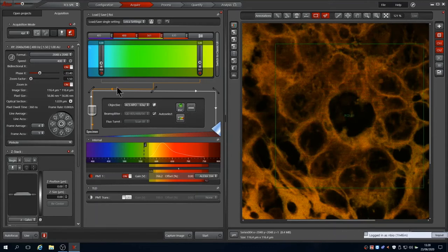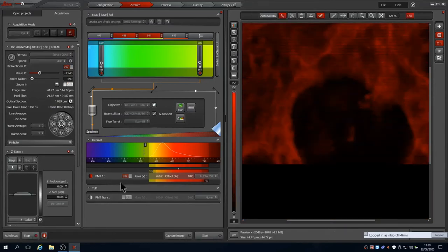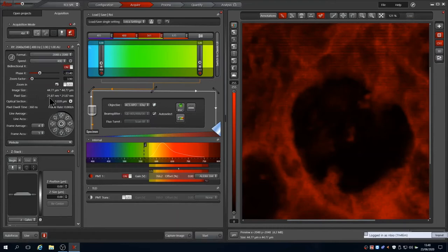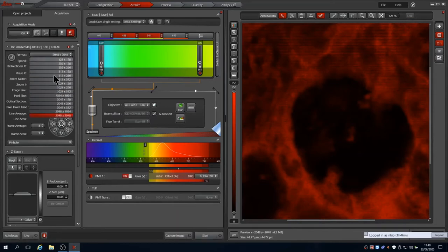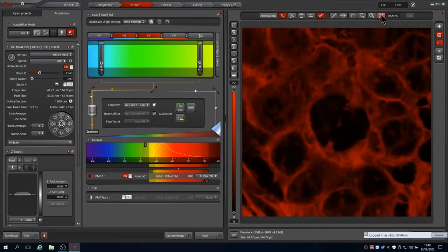The software will still keep the global XY parameters we set, so we'll still get a square scan to fit the area and at the same pixel density. This means our pixel sizes are now very small, meaning we are heavily oversampling. Therefore we can reduce the scan format. With this zoom, 1024x1024 works well to allow satisfying Nyquist. To visualise the whole scan area, I reset the zoom using the auto fit icon on the top right and capture a scan of this plane.